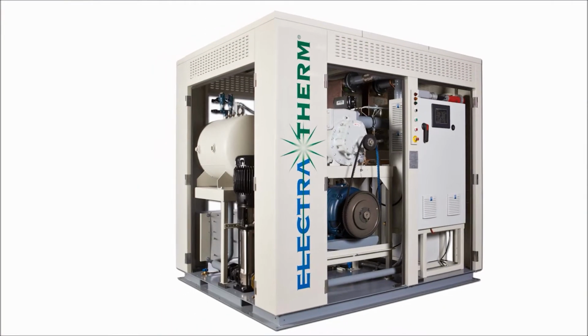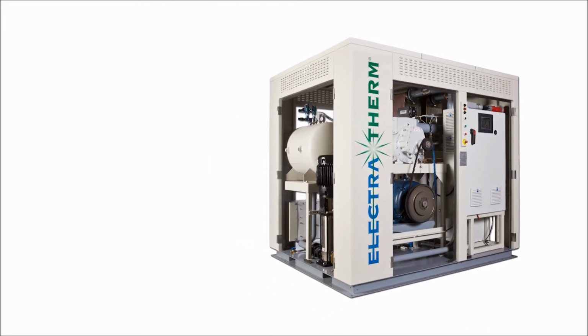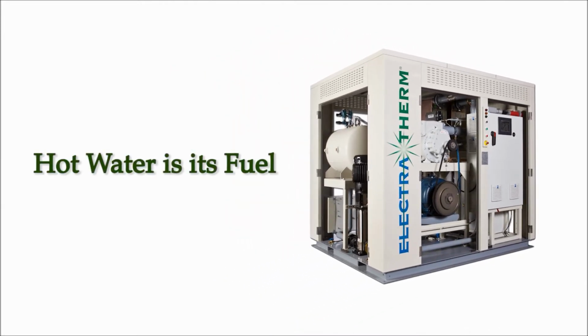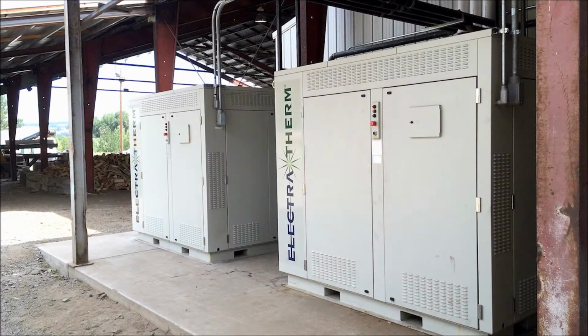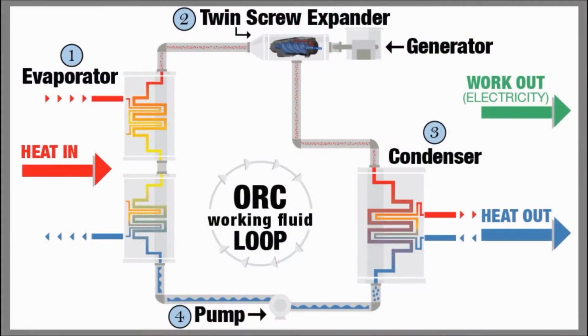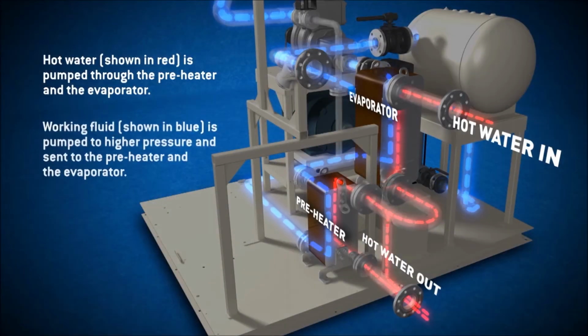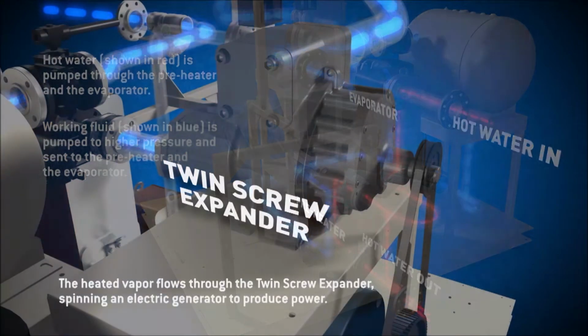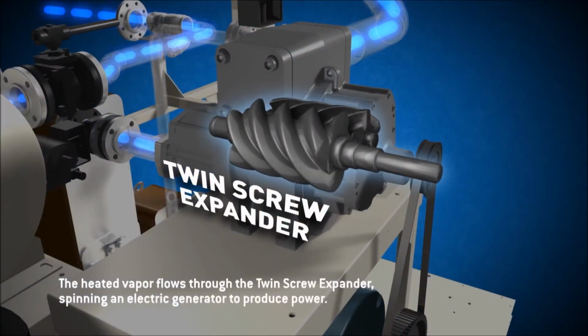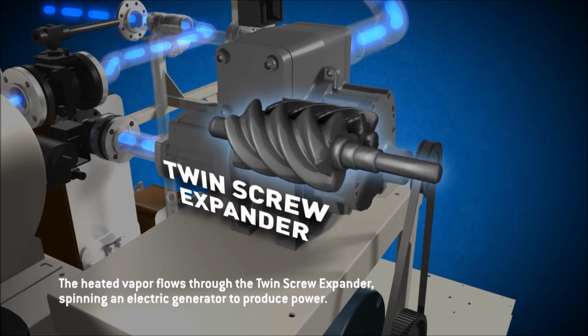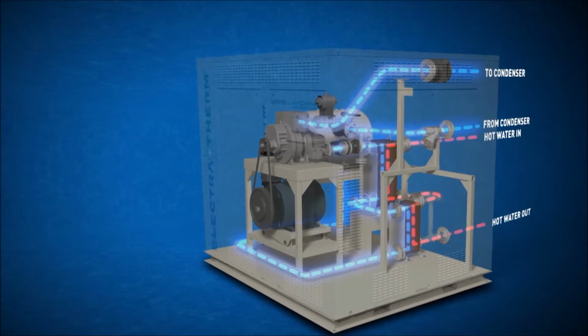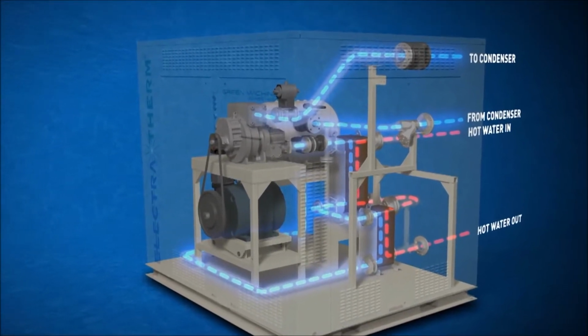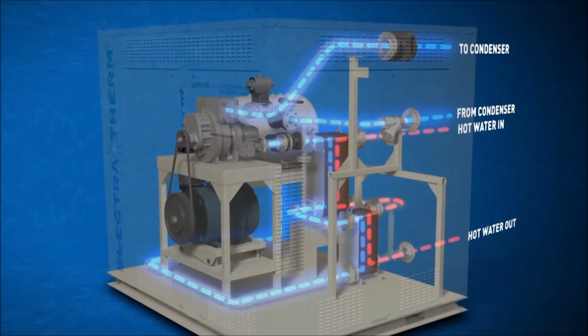The Power Plus generator produces clean energy from low-temperature heat. Hot water is its fuel. The Power Plus uses a closed-loop organic Rankine cycle, also known as ORC, to create pressure by boiling the working fluid into high-pressure vapor. The gas turns a twin-screw expander, which drives the generator to produce electricity. The electricity can either be sold to the grid for profit or used on-site to offset power costs.